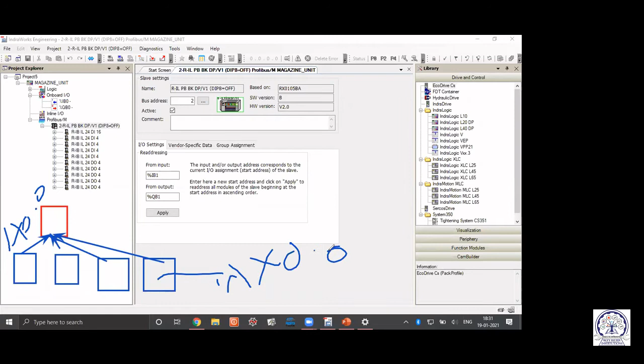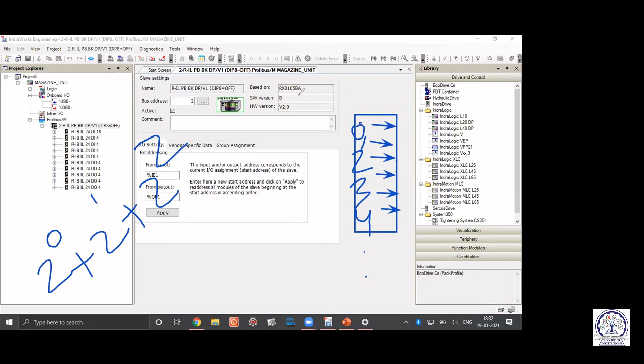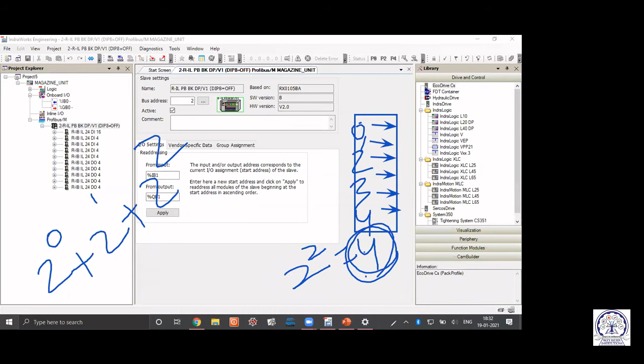Here are some switches, and for these switches you can add powers of 2: the first is 2 to the power 0, then 1, 2, 3, 4 like that. So if a switch is on, you add 2 to the power 0, plus 2 to the power 1, plus 2 to the power 2, and so on. Say the third switch is on, that is 0, 1, 2, so the address will be 2 to the power 2, which is 4. So the address for the Profibus slave, or the Profibus module, is 4. So we have to put that address.